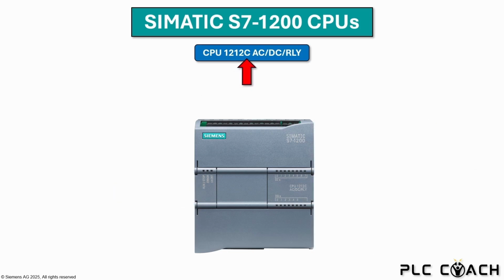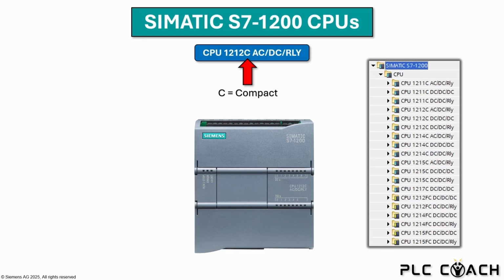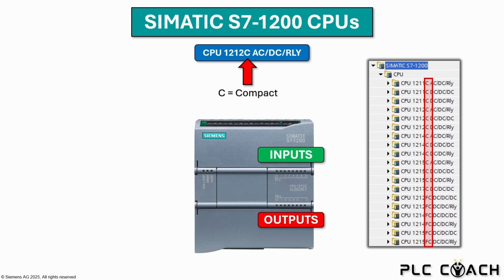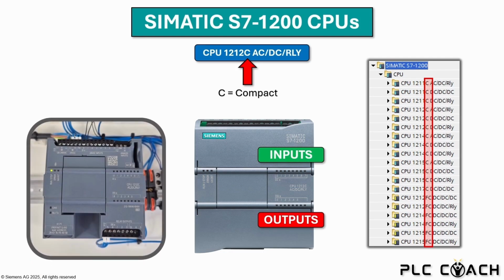Every S7-1200 is a compact CPU. This means that the controllers always have pre-installed inputs and outputs, which differ in the number and type. No front connector is required. The terminals are pre-installed at the factory. Some of the Simatic S7-1200 CPUs can also be used for safety functions such as emergency stop.